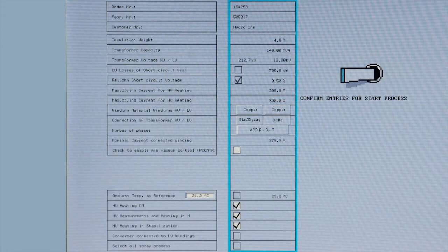The connection procedure is very rare and should only be used when it is not possible to connect to the HV winding, or the current density of the LV winding is much lower than the HV winding. In all normal cases, the HV winding should be connected since it can be difficult to reach nominal current on the LV winding. Select oil spray process.